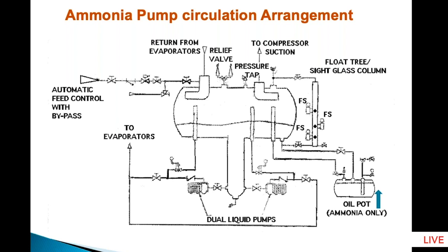There is no problem. This LP vessel helps us to separate the system into two components. One is the refrigeration system and one is your process system, in which liquid ammonia is used as a utility. The process could be IQF, or it could be a blast freezer, a plate freezer, air coolers, anything.